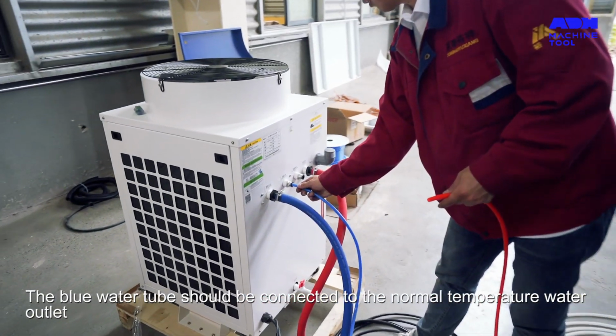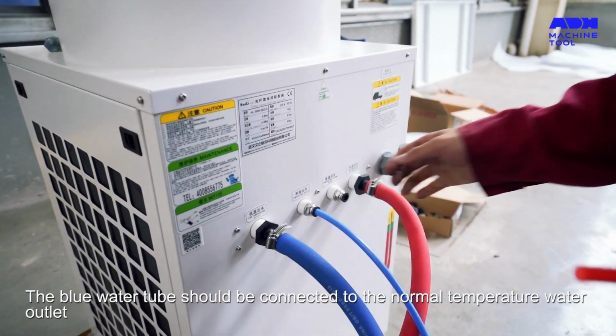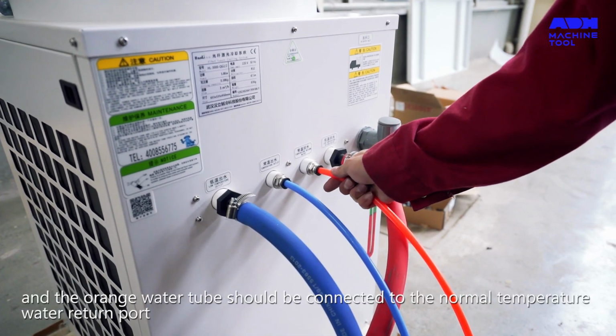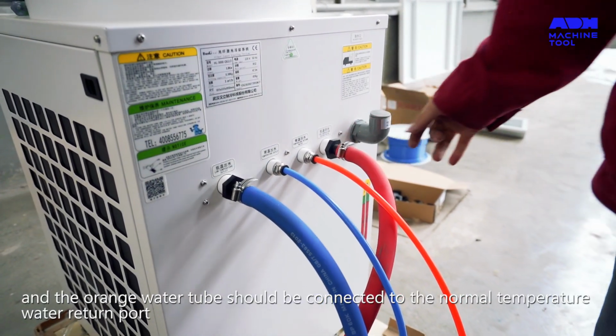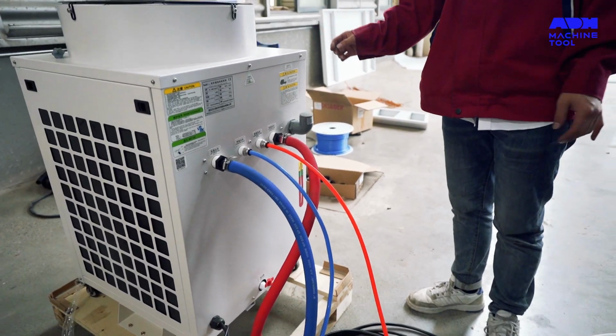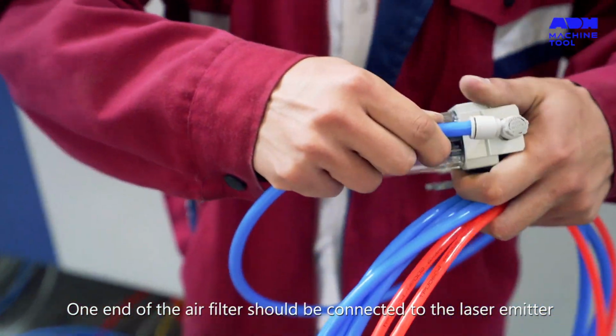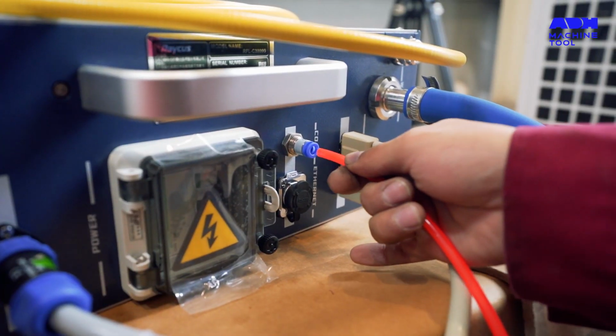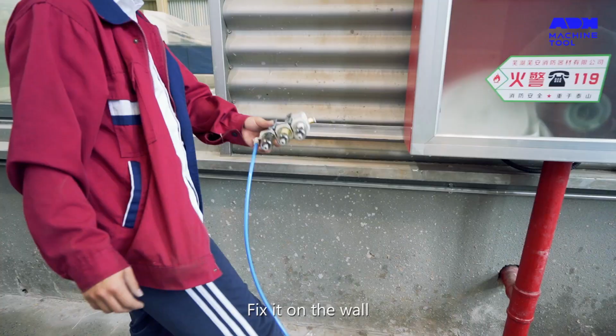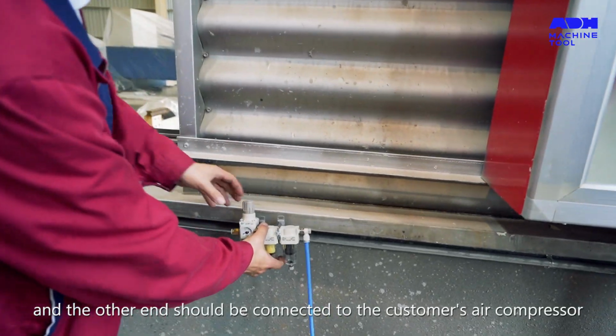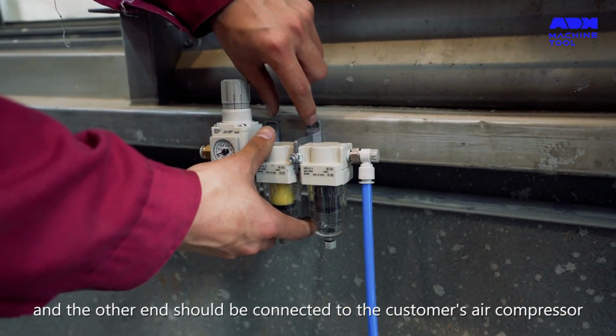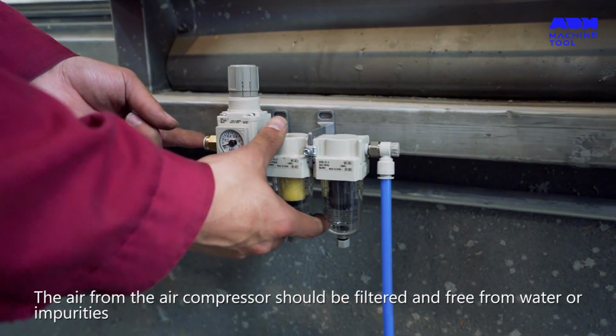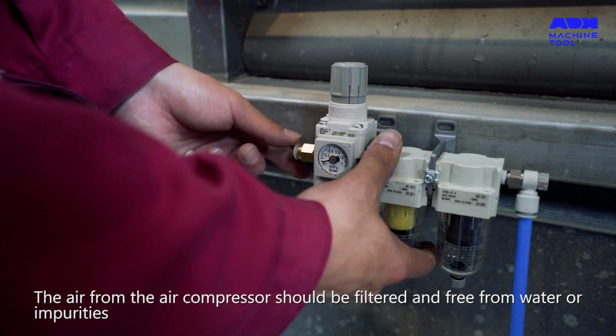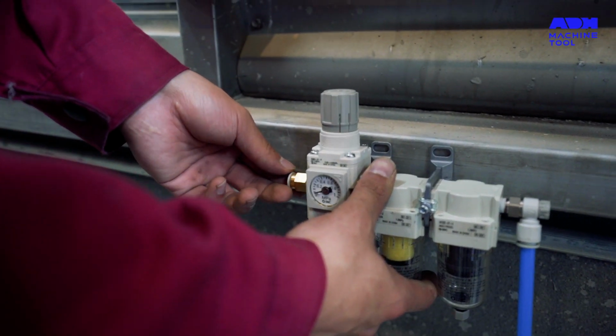The blue water tube should be connected to the normal temperature water outlet, and the orange water tube should be connected to the normal temperature water return port. One end of the air filter should be connected to the laser emitter, fixed on the wall, with the other end connected to the customer's air compressor. The air from the air compressor should be filtered and free from water or impurities.